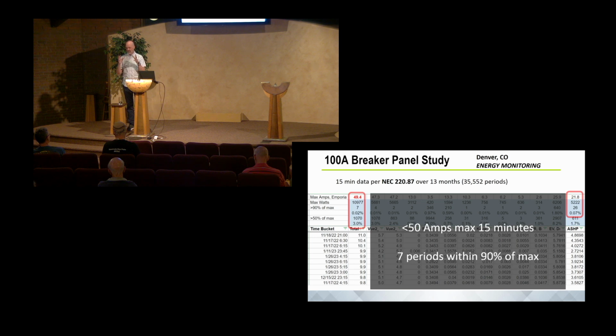It can turn things off as you get indications that you need to manage power a little bit more, or maybe you just want to manage costs. There's a lot of things you can do with the Span panel, and they come in 100 amp and 200 amp versions. You can easily do a 100 amp plus power, 200 amp breaker with power monitoring and the load shedding that Span does.